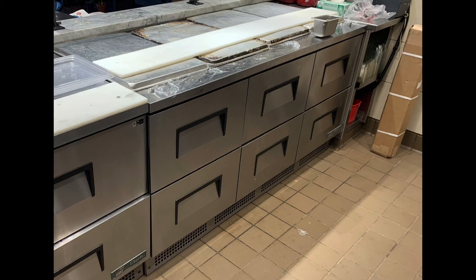Once you make sure that all the drawers and everything are working properly and nothing is getting snagged, you should have your unit getting back down to temperature. Every now and then there will be something else going on, but you have to address the air infiltration first — whether it's the middle mullion, the gaskets, or somebody leaving the drawer open. That particular unit needs to remain closed when not in use so it can get back down to temperature and keep the food at the right temperature.